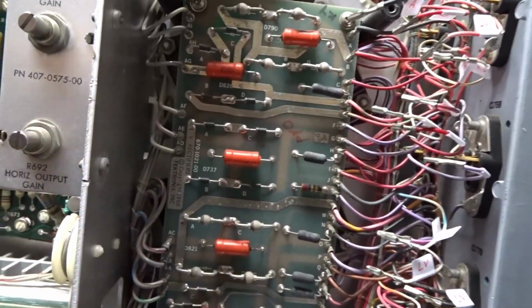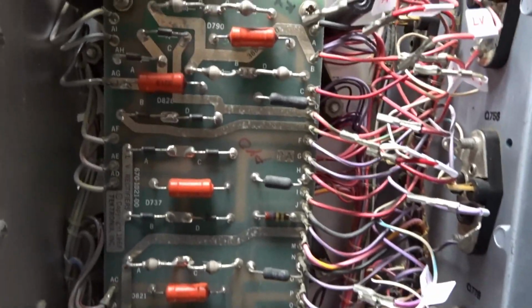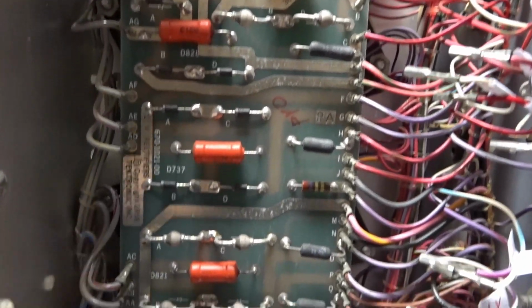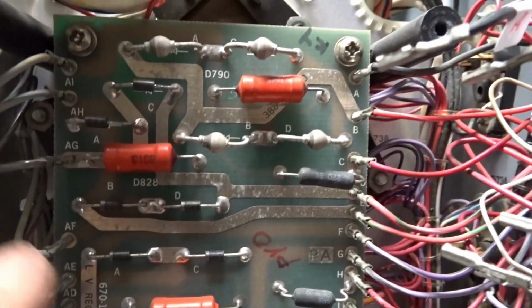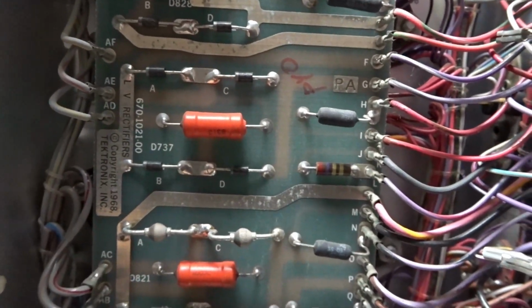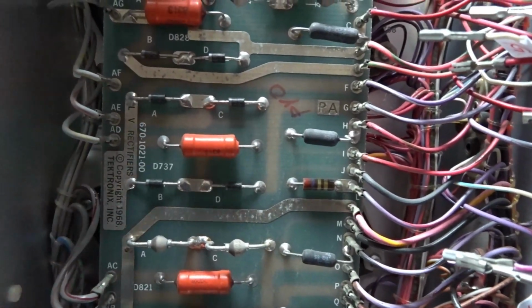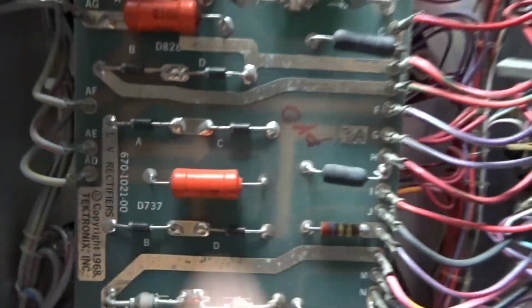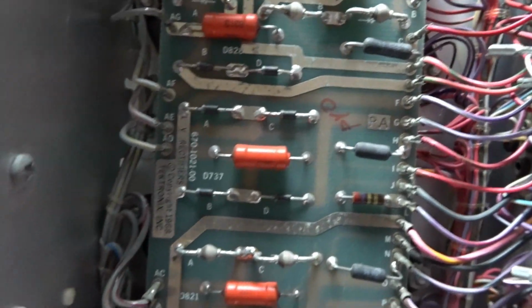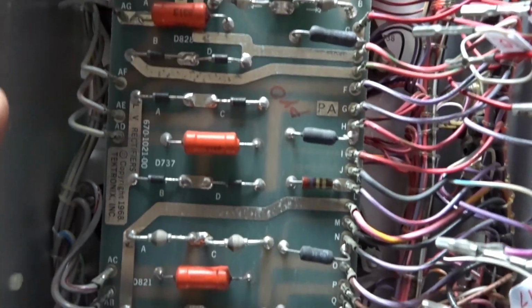Okay, I removed the low voltage regulator board. Behind it is the low voltage rectifier board, and there are these orange ones, which are capacitors also. So I'm going to check the diodes and capacitors to make sure they are okay, and the rectifier capacitors are behind this board, so I have to remove this board. As you can see, there are these cables on both sides. I have to remove at least one side of the cables, mark them again, and remove them to get access to the capacitors. Sounds fun.